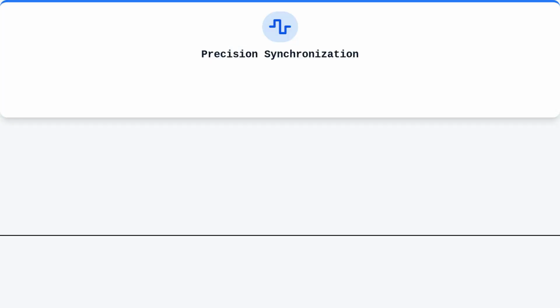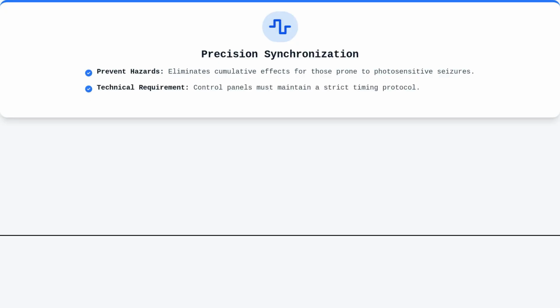Strobe light synchronization serves as a vital mitigation strategy for occupants prone to photosensitive seizures. When multiple strobes are located within the same field of view, it is mandatory that they flash in tight synchronization to prevent the cumulative effect of disparate flashes. From a design perspective, this necessitates that the control panel or the appliances themselves possess a timing protocol that maintains a consistent flash rate and phase.